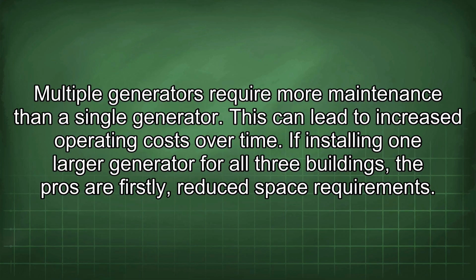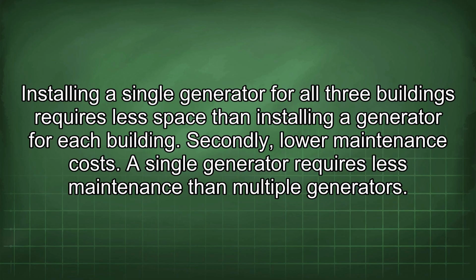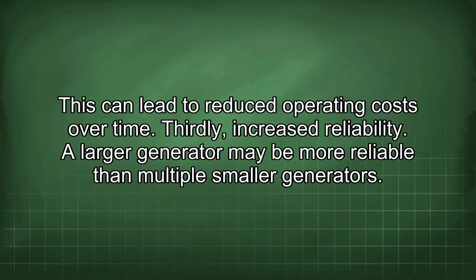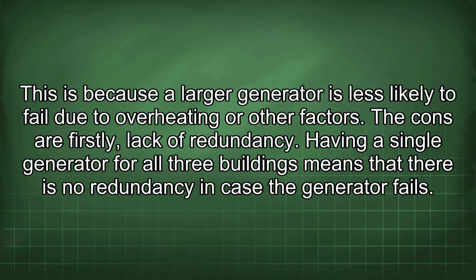If installing one larger generator for all 3 buildings, the pros are, firstly, reduced space requirements. Installing a single generator for all 3 buildings requires less space than installing a generator for each building. Secondly, lower maintenance costs. A single generator requires less maintenance than multiple generators. This can lead to reduced operating costs over time. Thirdly, increased reliability. A larger generator may be more reliable than multiple smaller generators. This is because a larger generator is less likely to fail due to overheating or other factors.